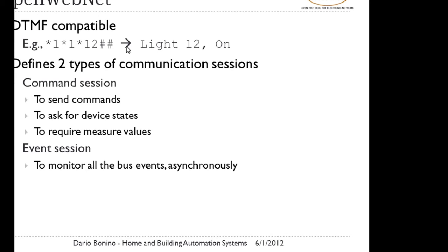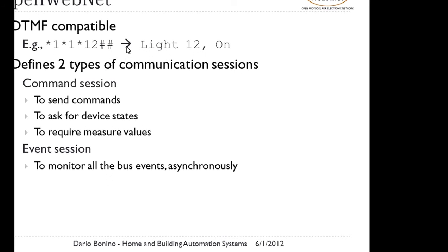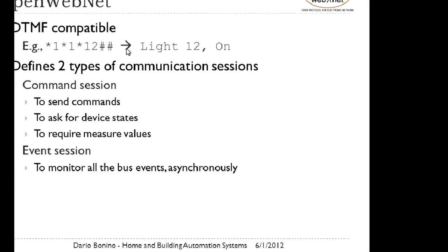And if we want to interoperate or integrate this technology, we need to open both connections, basically, because we need to listen to what's happening on the network, because perhaps we want to bridge the network towards another, so we want to listen that a button has been pressed, because we want to route the command to a KNX network. But on the other side, we need also to command the devices on the network. So from the requirements side, this technology requires two sessions open at the same time, if we want to interoperate and integrate.